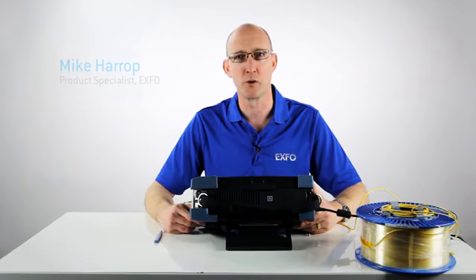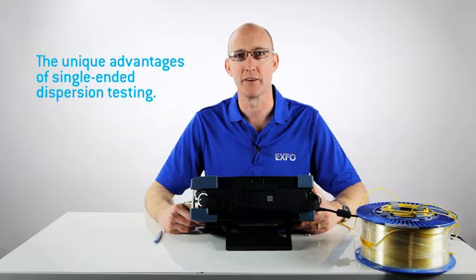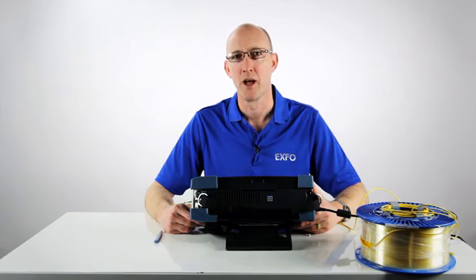In this video I'm going to demonstrate EXFO's single-ended dispersion tester, the FTB 5700. As we know, chromatic and polarization mode dispersion can be real system limiters for 10 gig and 40 gig non-coherent systems and can still cause issues with the new 100 gig systems. So, knowing the CD and PMD of the fiber is still very important.